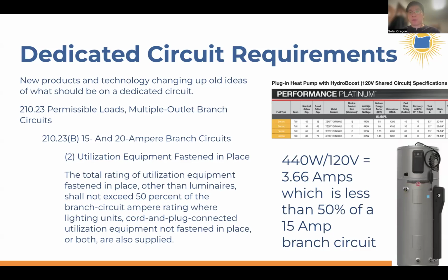These heat pump water heaters, as you see in the spec sheet, use 440 watts. If you do the math, that translates to 3.66 amps, which is way less than half of 15 amps. So they can definitely go on shared circuits, and you still have enough electricity in that circuit to power your laptop, your cell phone, and maybe some overhead lights, etc.